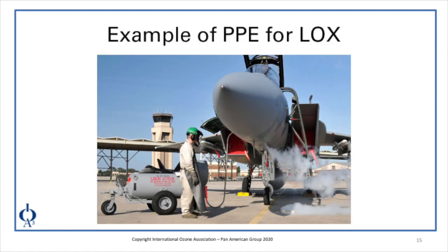Here's one example of personal protective equipment for use around liquid oxygen. We don't often have to work around open liquid oxygen, as delivery drivers are the ones connecting up and loading the tanks. When we do have leaks on the system, it is important to isolate at the tank if possible and not work when there is a leak in progress. When working in the vicinity of a liquid oxygen system, appropriate PPE includes a face shield, closed-toed boots, an apron, and cryogenic gloves to protect hands and skin from any exposure to liquid oxygen.